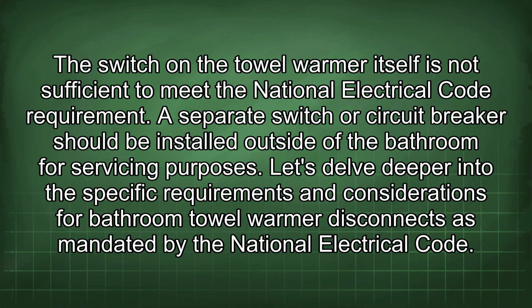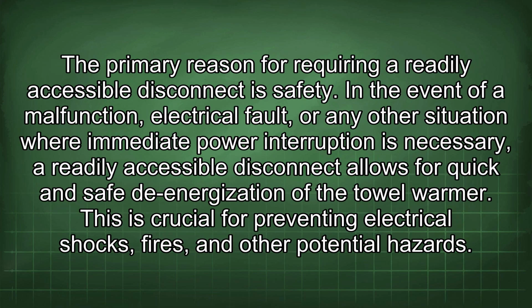Let's delve deeper into the specific requirements and considerations for bathroom towel warmer disconnects as mandated by the National Electrical Code. The primary reason for requiring a readily accessible disconnect is safety. In the event of a malfunction, electrical fault, or any other situation where immediate power interruption is necessary, a readily accessible disconnect allows for quick and safe de-energization of the towel warmer. This is crucial for preventing electrical shocks, fires, and other potential hazards.